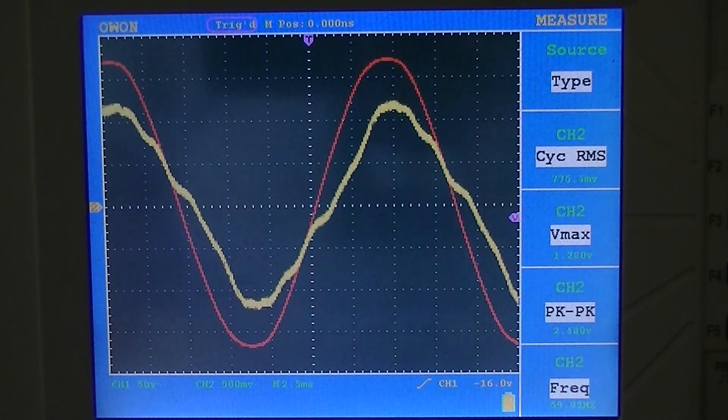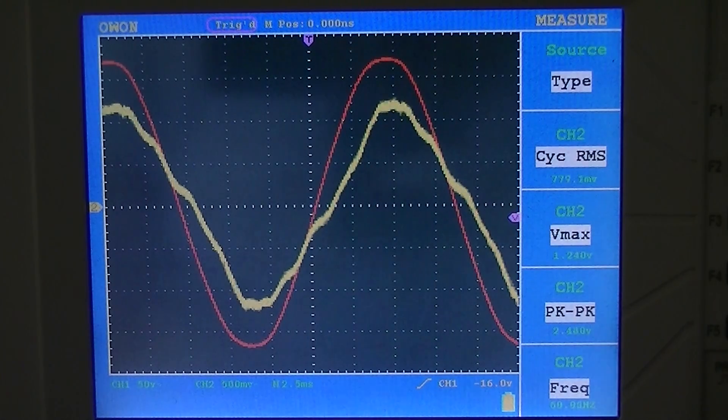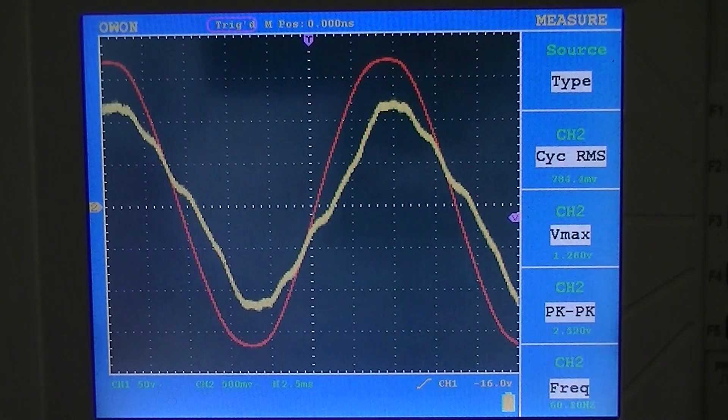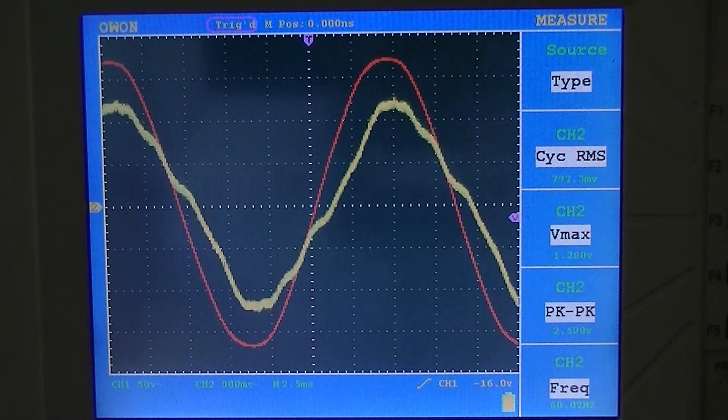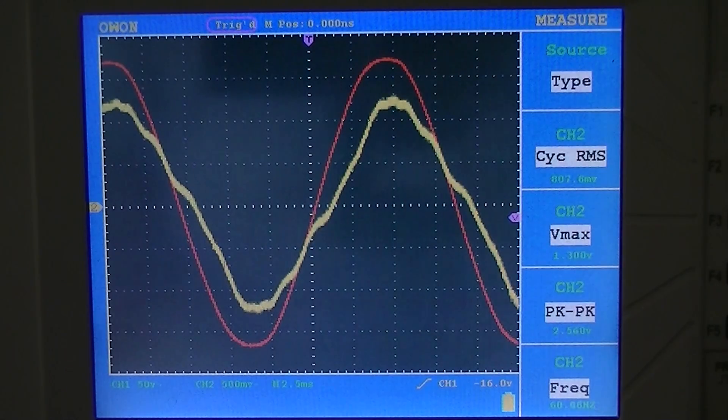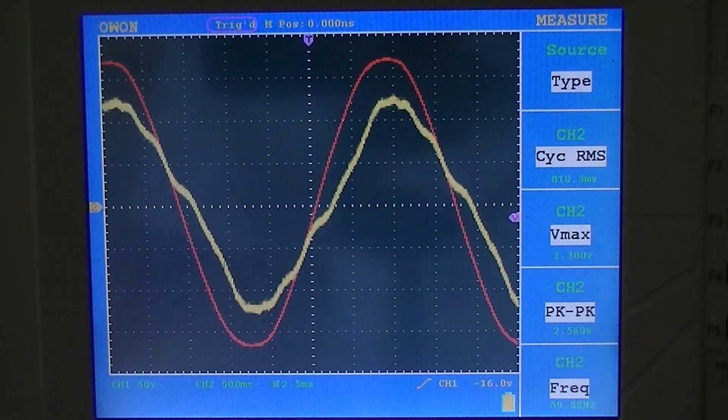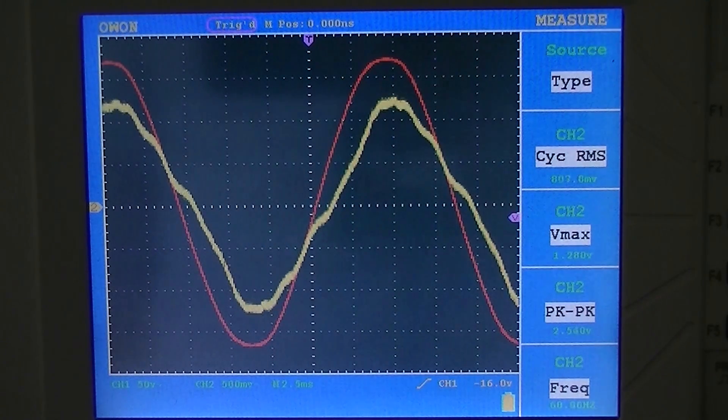Now, I actually see this peak up to 1.6 volts in summertime. And it gets really hot and everybody's running their air conditioning systems. And it's 110 degrees there. I'm seeing 1.6 volts on my electrical grounding system. And what that translates to is 132 amps is what I would have to pass down the neutral system to generate 1.6 volts, assuming that the other end of the neutral cable at the transformer is at 0 volts.